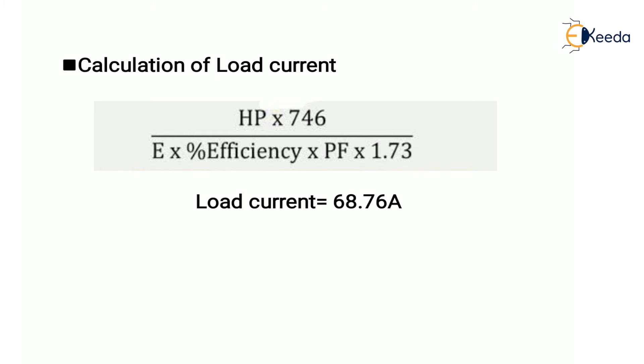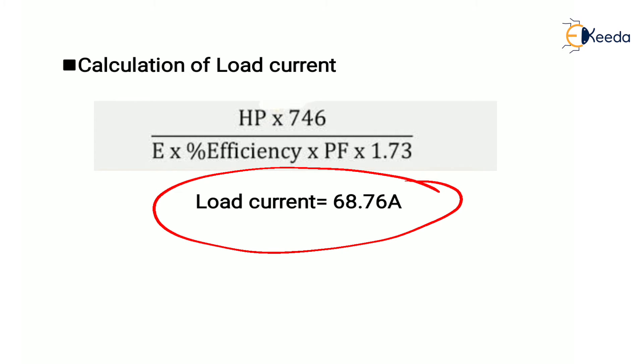Selection of the cable is based upon current carrying capacity, voltage drop, and short circuit rating. First, we calculate the load current using the formula: HP × 746 divided by (√3 × voltage × efficiency × power factor). We have 45 HP, so multiplying by 746 and dividing by √3 × 415 × 0.85 × 0.8, we get the load current as 68.76 amperes.